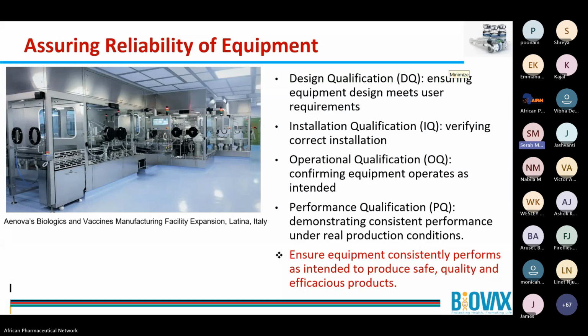There are also requirements for the computerized systems that will be coupled together with the equipment. You have to ensure that you have validated those computerized systems, and you have documentation for that. You have to keep a record of that. And then you should have a way of retiring the equipment, and you have to plan ahead to procure this equipment. Most of them have what they call programmed obsolescence. And so at the end of maybe 10 years, you will have to start planning how to replace some of this equipment. And you can only do this if you have a proper schedule and program for preventive maintenance, so that you can know when the manufacturer is phasing out a certain equipment, so that you don't run into the trouble of not getting some parts because some of the equipment are already obsolete.